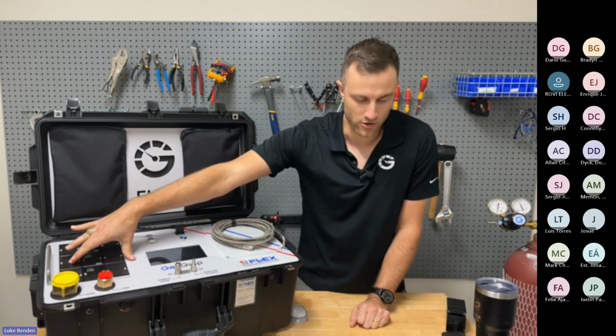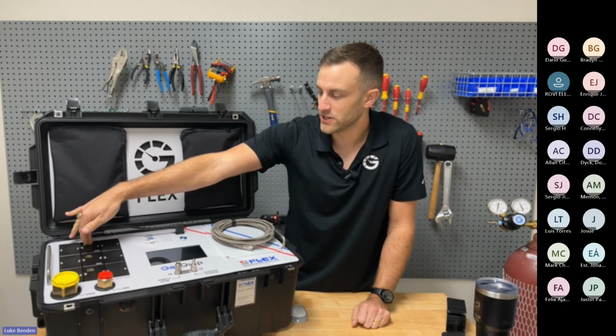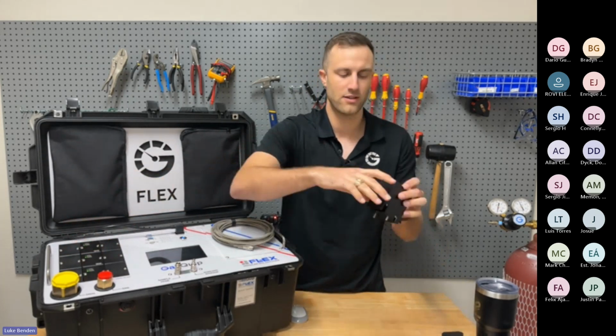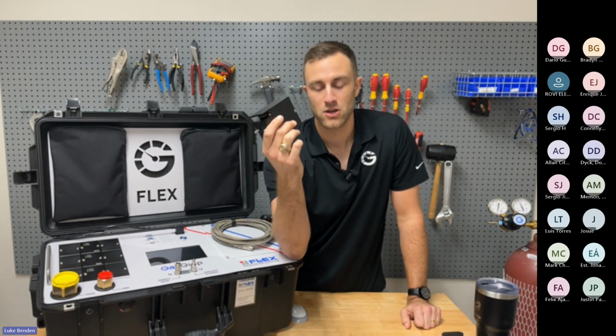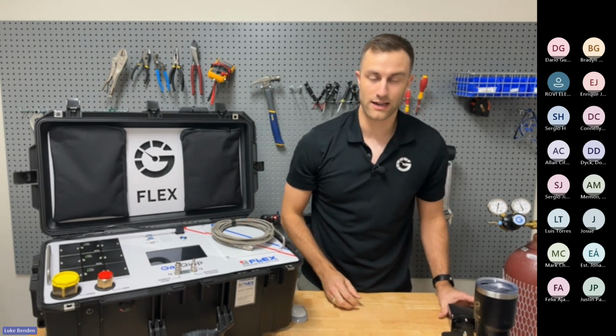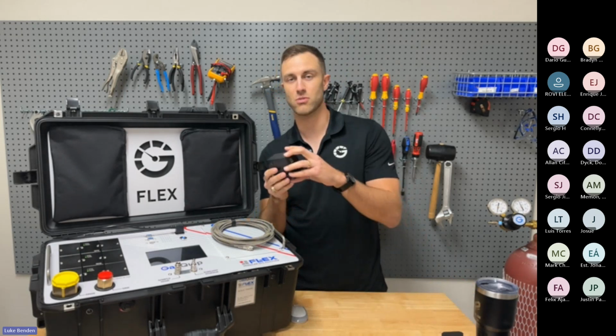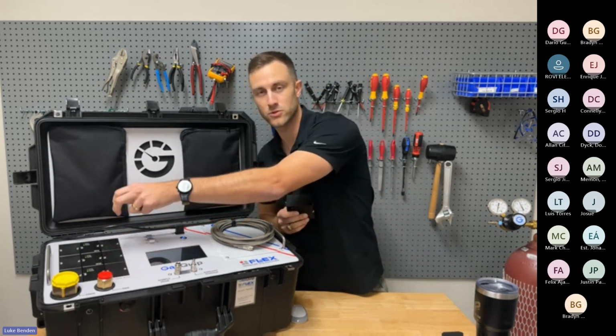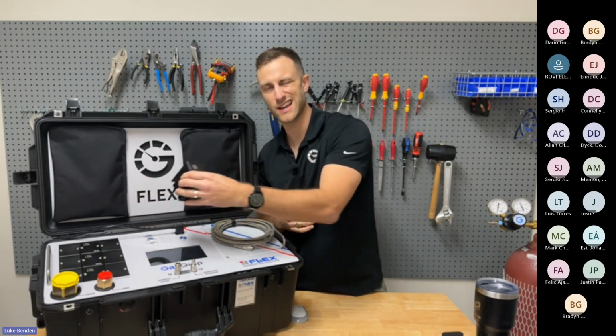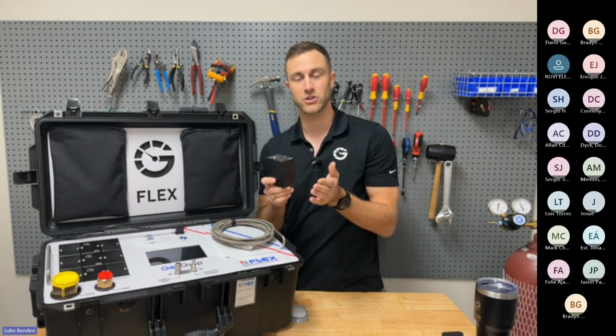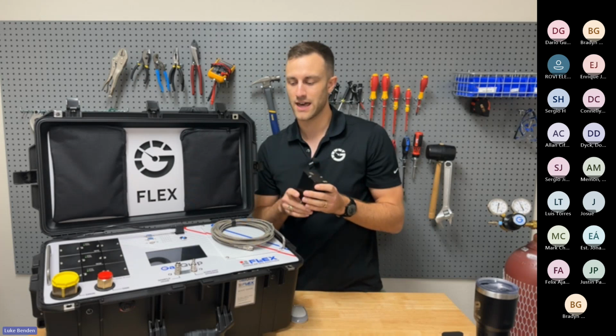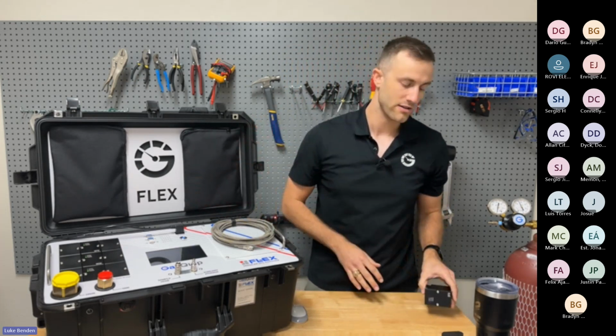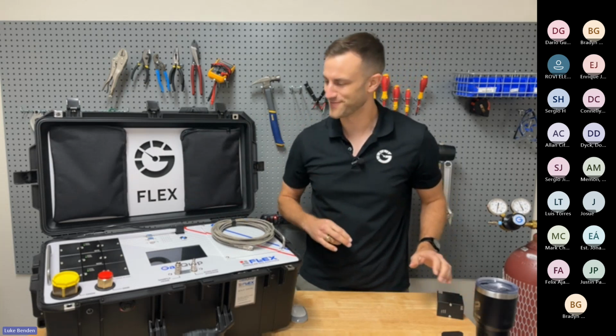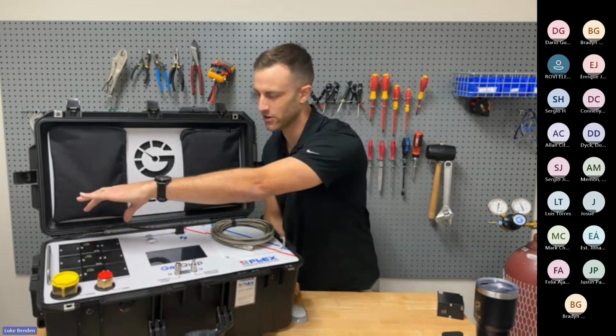Up here you have our sensor module manifold. We have 3 sensors that sit in a module like this. The reason we did that is so that when it's time to have your device calibrated, you no longer have to send it back to us. We basically just send you a replacement sensor module. You pop out the old one with a little torque wrench, pop in the new one, kind of like a printer cartridge, and you're good to go. All the calibration data is stored on the module itself, and it'll pull up on the device automatically. Never have to send the device back to us. Fingers crossed.